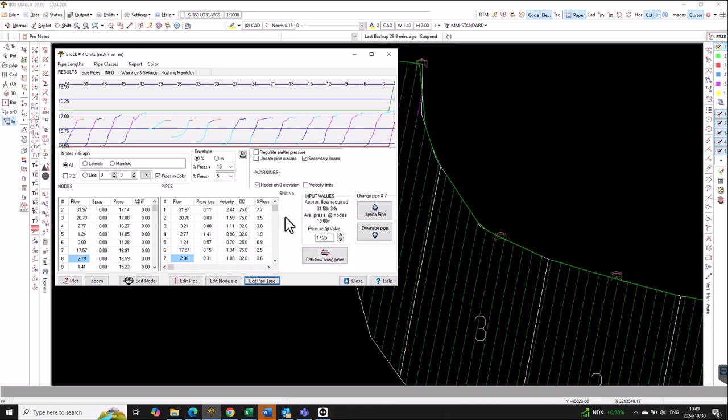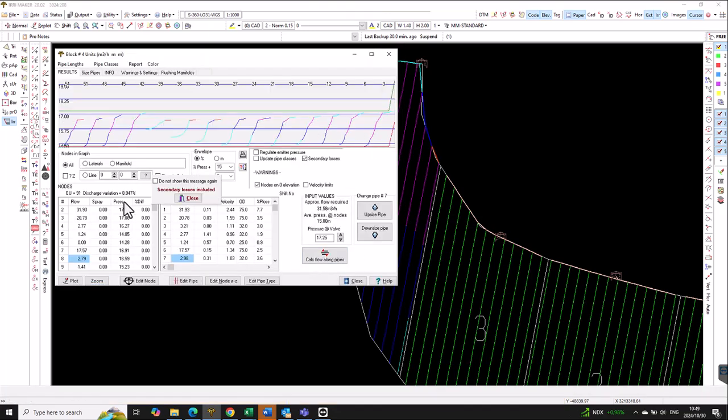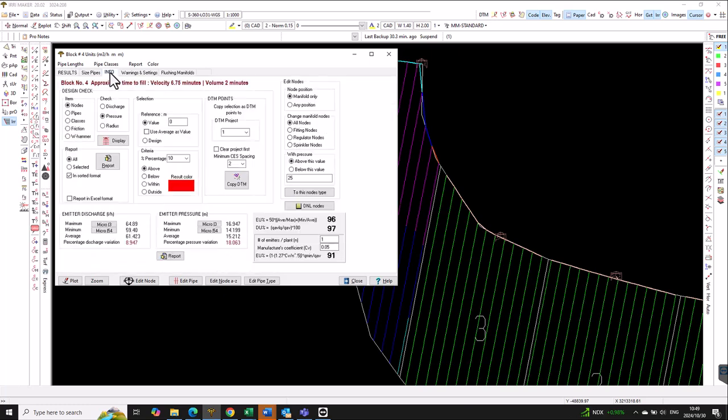Okay, so that affected my design. Hydraulically we are now at 9. Wow, even better. Yeah, because we got rid of the ones at the top. So there's the flow, it's improved actually. We took a whole bunch of 12s and 15s and made them 20. Now if I go to info, I can see my minimum flow is 59, my maximum flow is 65, average is 61.425, it's 8.9 flow variation. We are so happy about this, it's perfect.